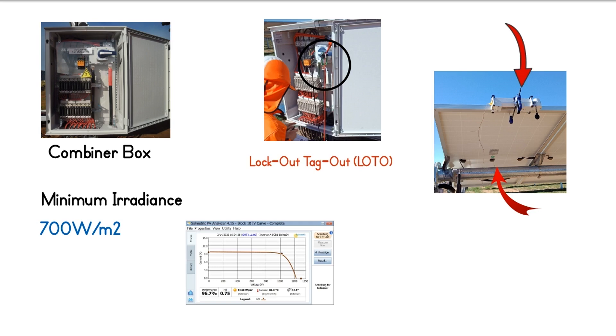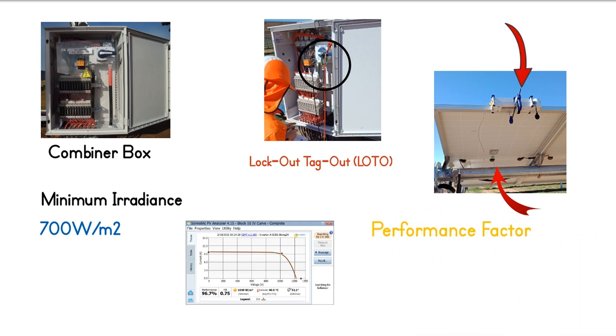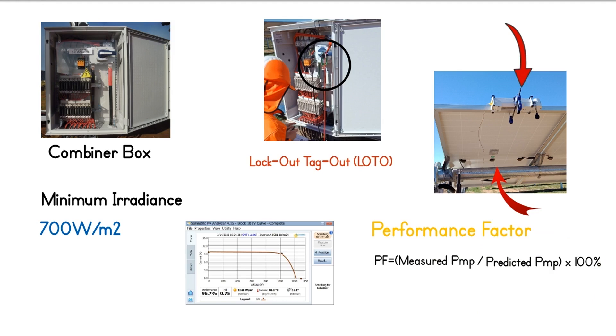The degree of how well the measured IV curve agrees with the predicted IV curve is known as the performance factor, expressed as a percentage. The equation to calculate performance factor is: PF equals measured PMP divided by predicted PMP times 100%.